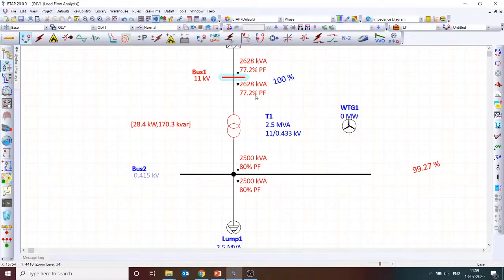You need to maintain the power factor, and it varies from utility to utility; they will have a different tariff for power factor. At least at 11 kV, you need to maintain a power factor of more than 0.9. That is the rule. But now you are not able to maintain 0.9; you are maintaining only 0.77. For that, you need to put in a capacitor bank. But my concern is not that.